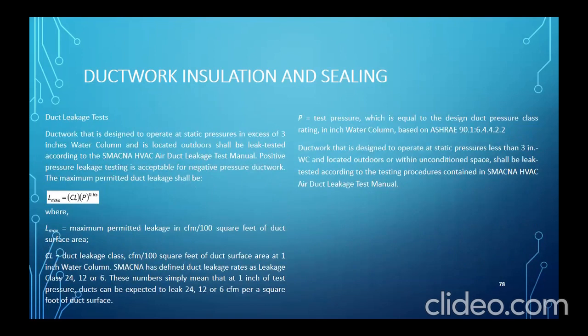So duct leakage test. So ductwork that is designed to operate at a static pressure in excess of 3 inches water column and is located outdoors shall be leak tested according to SMACNA HVAC Air Duct Leakage Test Manual. Hanapin niyo yung book na yan. So positive pressure leakage testing is acceptable for negative pressure ductworks.